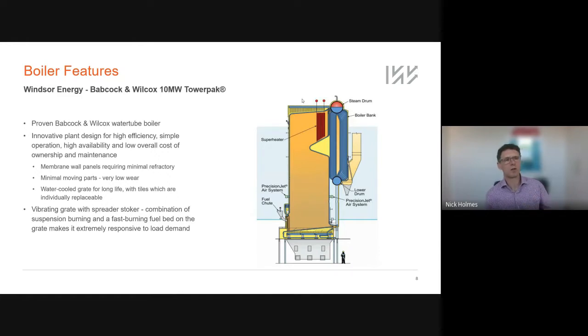So you have a long residence time in the boiler. It's very important to have lots of overfire air to get the turbulence. And the temperature is the combustion temperature, getting that as high as you can before you run into potential fouling problems with clinker.